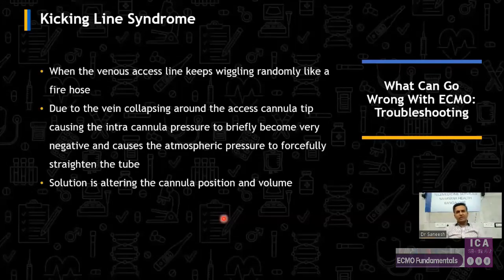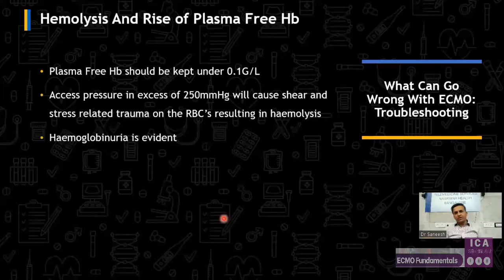What is kicking line syndrome? When the venous line keeps wiggling randomly like a fire hose. This occurs due to the massive negative pressure, which causes the vein to collapse over the access cannula tip and causes the atmosphere pressure to straighten the tube. The solution is alter the cannula position and correct the volume status, and this will be sorted out.